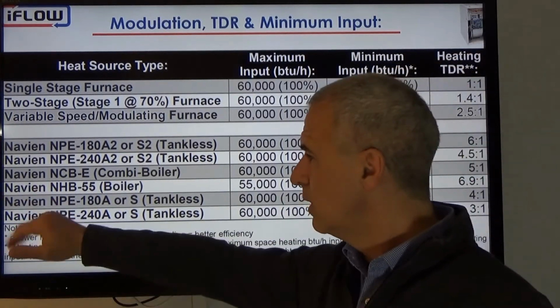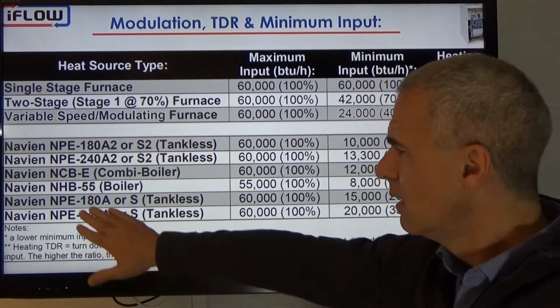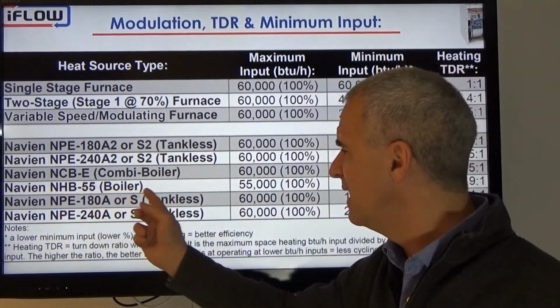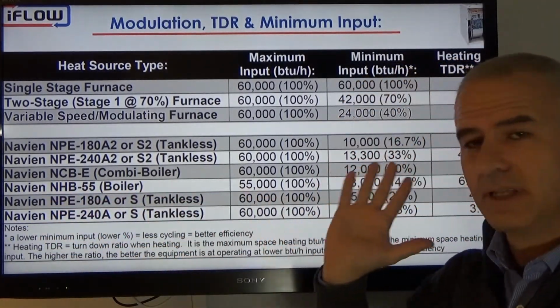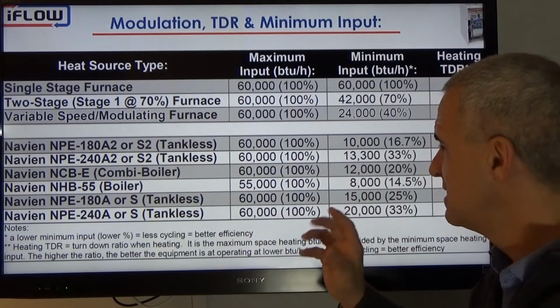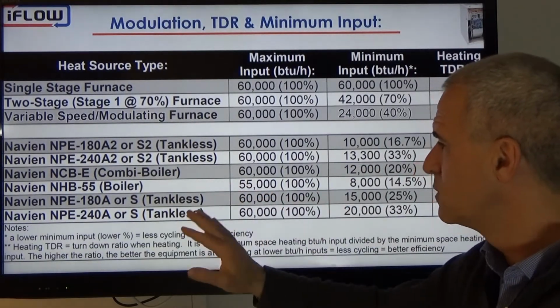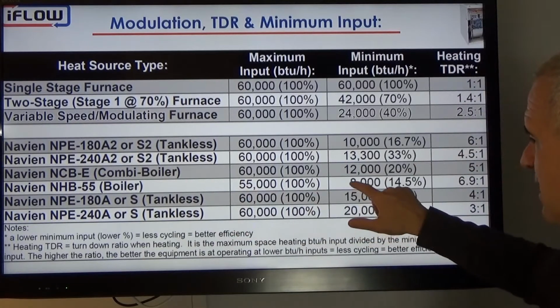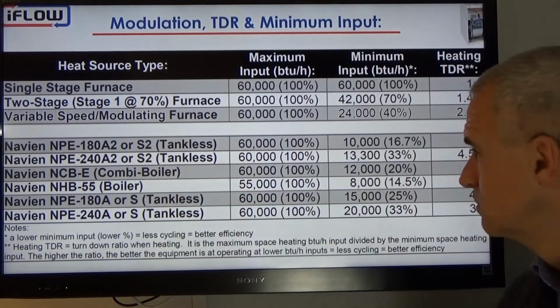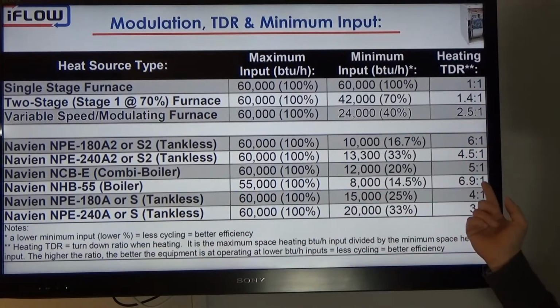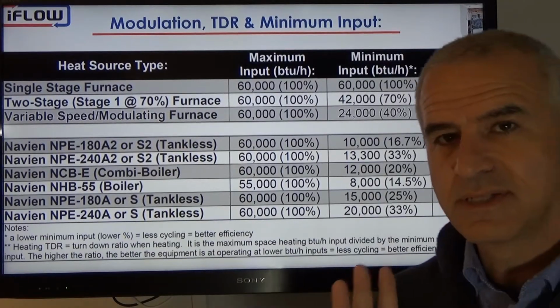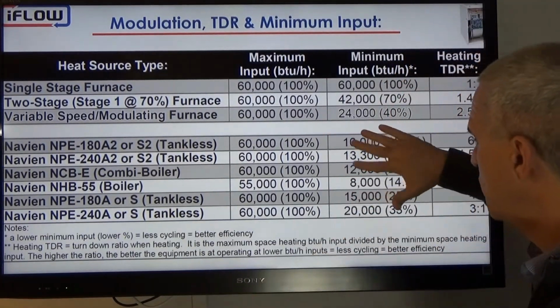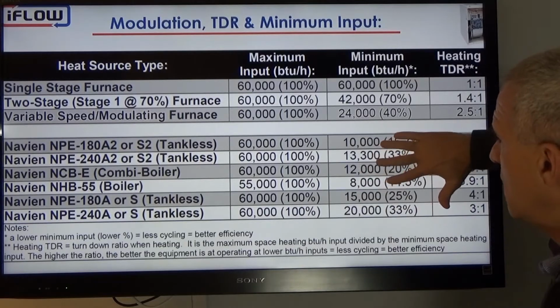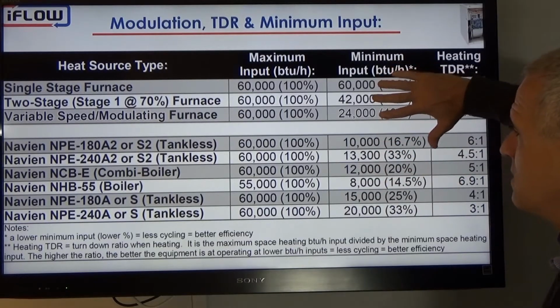Now let's look at the boiler side. Let's look at the NHB-55, for example. 55, fairly close to 60, so I just put in, it's not 60 exactly, but it gives us a good reference point nonetheless. It's down to 8,000 BTUs, giving us a turn down ratio of 6.9 to 1. So all to say, the minimum inputs on the Navien side are much lower than the furnace side.